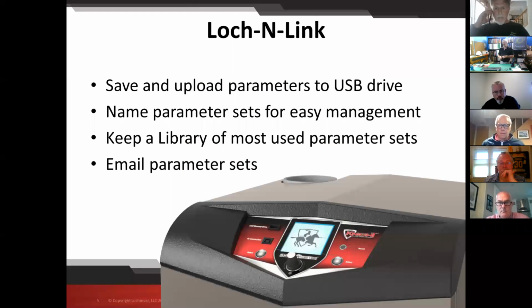Loch-N-Link, it's a feature that came out with the latest generation of the smart control, 2014-ish. That gave us the ability to plug a USB thumb drive into it. So you can have programming pre-programmed on a thumb drive. We make available from us thumb drives that have some generic, if you will, programming. You'll put it in and you'll say, hey, I got baseboard, I got hydro air, I've got radiant. It's going to give you some very general conservative settings. Just a good thing to, hey, you don't want to struggle setting up the control. You don't want to go through all that. Boom, I'll just put that in there and it'll be done. Take you about 30 seconds.